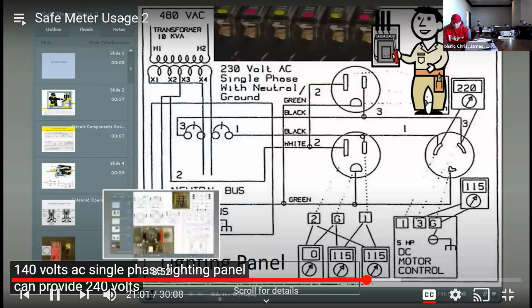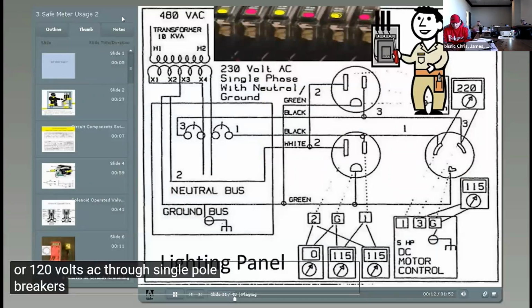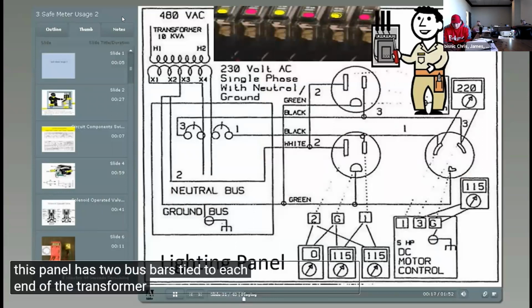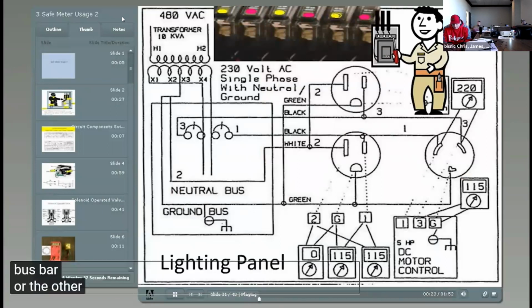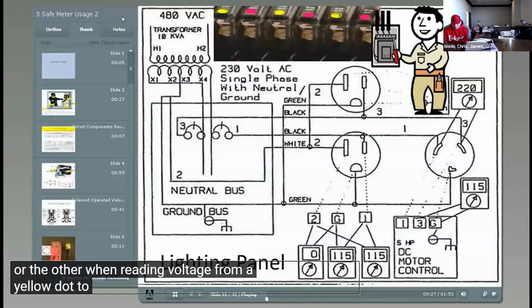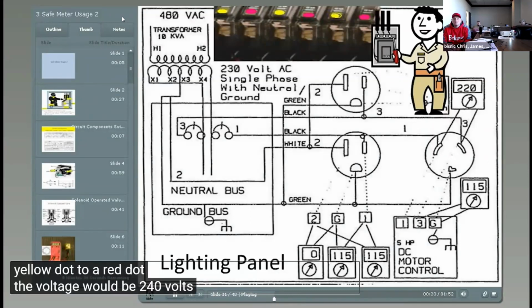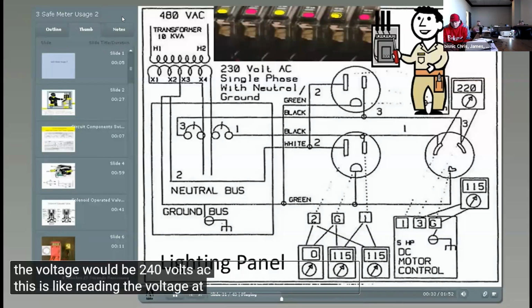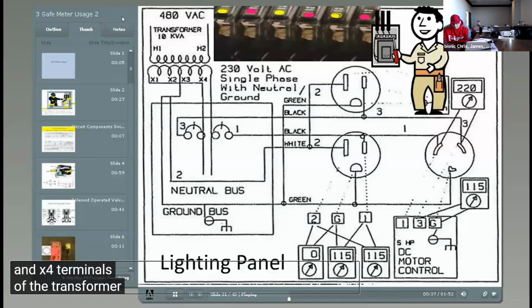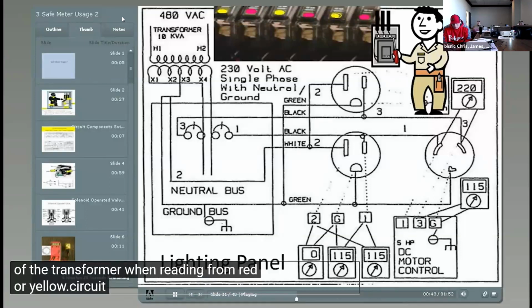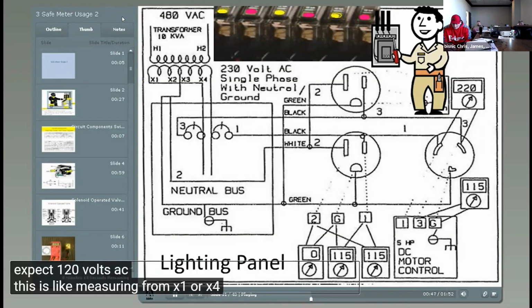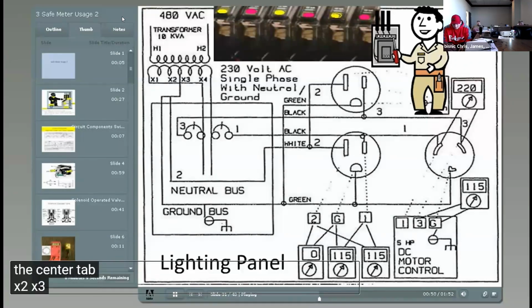A 240 volt AC single-phase lighting panel can provide 240 volts AC through double pole breakers or 120 volts AC through single pole breakers. This panel has two bus bars tied to each end of the transformer. Every other feeder circuit breaker usually snaps onto one secondary voltage bus bar or the other. When reading voltage from a yellow dot to a red dot, the voltage would be 240 volts AC. This is like reading the voltage at X1 and X4 terminals of the transformer. When reading from red or yellow dot circuit breaker to ground, expect 120 volts AC. This is like measuring from X1 or X4 to the center tap X2, X3.